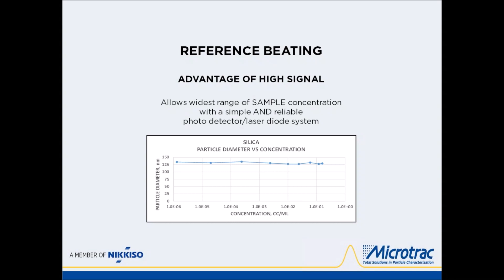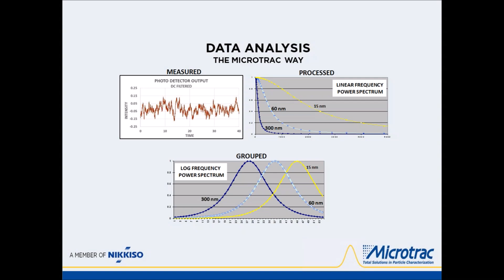Once we've gathered the data, now we've got the signal, the algorithm takes over. We've taken our raw signal and it's gone through a fast Fourier transform, linear frequency power spectrum, to produce these sort of lines from top left down to bottom right. And when we log frequency those curves again, instead of having lines that we've got to deal with, now we have curves that have an actual inflection point that gives us a much better analysis when it comes to separating out large particles versus medium particles versus small particles.